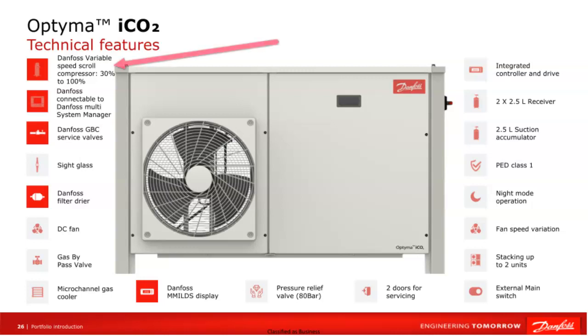This unit is equipped with a scroll compressor with adjustable capacity ranging from 30 to 100%. It is also possible to connect it to the system manager. The unit includes a gas bypass valve and a microchannel condenser. It is equipped with a display, a relief valve, an integrated inverter for the compressor, and a controller. Additionally, it has two liquid receivers with a capacity of 2.5 liters each. The fan speed is adjustable and there is a 2.5-liter suction accumulator on the inlet. Importantly, it is possible to stack the units on top of each other, which may be useful in some installations.